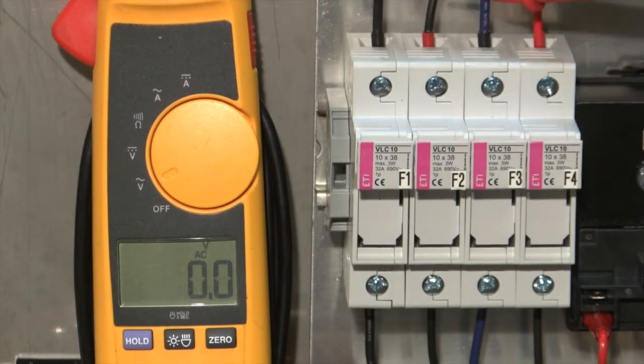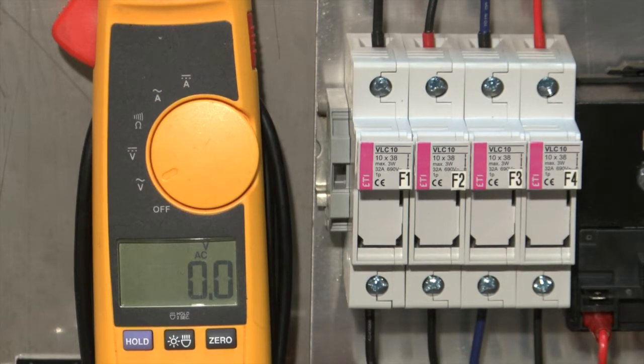Black is 120 on the primary side of the transformer. Blue is 48 volts on the secondary side of the transformer. And red is 24 volts on the secondary side of the transformer. To verify a fuse is good, use your corresponding neutrals on the transformer as discussed.